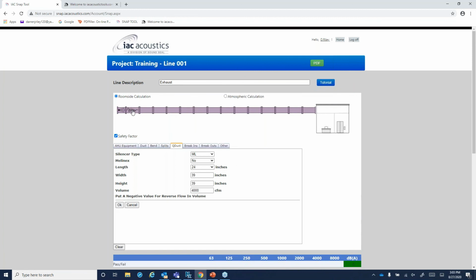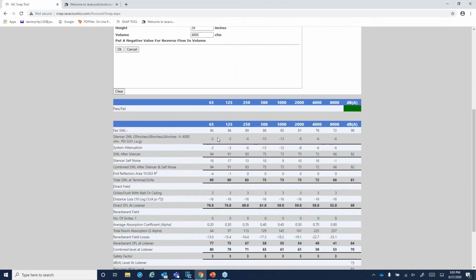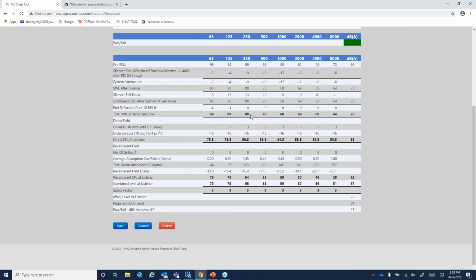So let's click OK, and you'll see that these are designed, and it starts out with pressure drop, the model, and the length. These will always populate from length, from shortest to longest. Now, in this specific example, the ML was selected, but I had to change it to 3 feet because that's what was asked for in the example. And you can see here is your criteria. Click OK. And we are at 11 dBA plus. So it's basically a pass-fail. Pass means it's green. Red means it fails. So look down here as you go through this, you're going to see here's your silencer and all the performance characteristics.